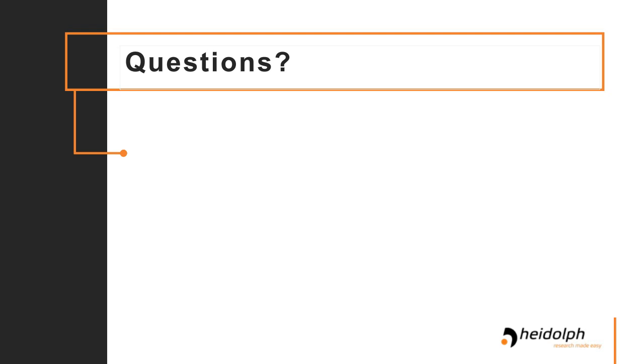Well, I can take over that question. The maintenance depends also a little bit on how often you use your evaporator, but entire cleaning should be done at least every 6 months, I would say, also to avoid any contamination and things like that. But of course, basic maintenance should be done frequently, nearly every day or every week, to clean the most important glassware parts. It also depends on your requirements regarding the purity of your final solvents, for example. Okay, thank you.